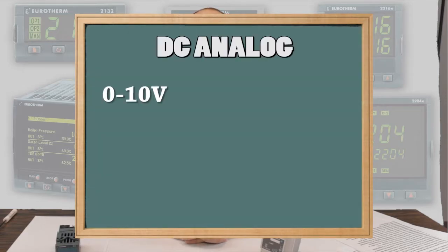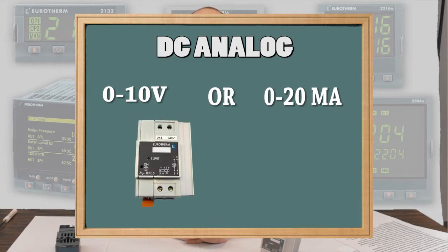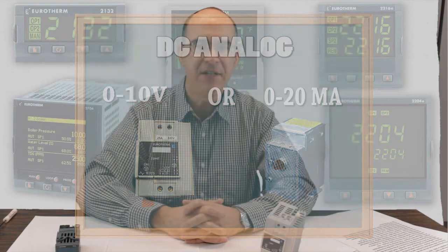The DC analog output type provides a variable analog signal, typically in the range of 0 to 10 volts DC or 0 to 20 milliamp DC. These output types and ranges are configured in the temperature controller to match the input signal requirements of the power controller. This type of output signal is usually used to control an SCR power controller or valve. The higher the output signal, the more power is applied to the load.